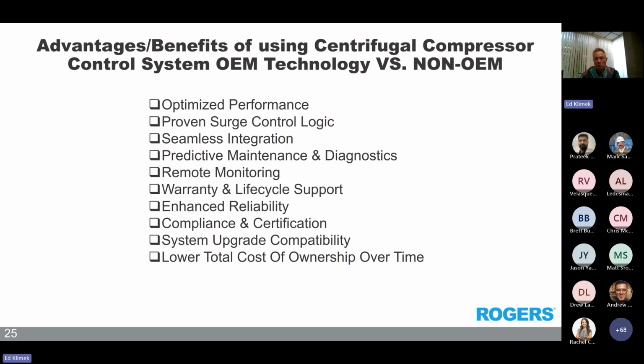Well, OEM systems are specifically engineered to match the compressor's aerodynamic design and performance map. This guarantees higher efficiency and load control, surge avoidance, and energy management. Proven surge control logic. The benefit there is factory-tested surge algorithms, which are tuned to machine-specific dynamics. You have faster response times and reduce the risk of surge events and mechanical damage.